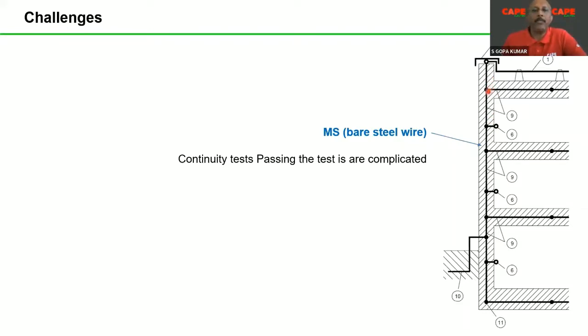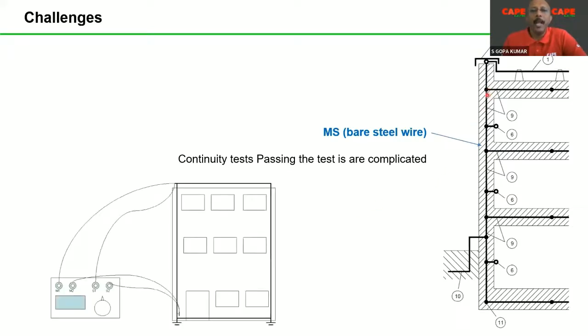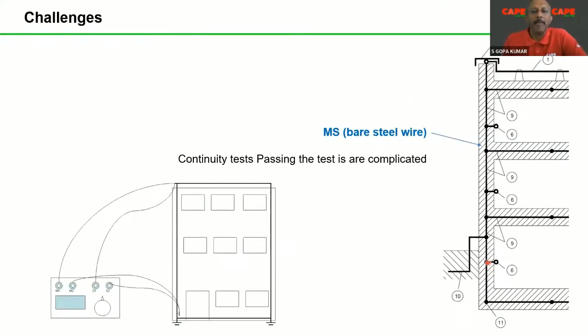In this case, out of our experience, what we are facing is after finalizing, after making this installation, we are supposed to check the continuity resistance. In several cases, the continuity resistance check is failing. Using MS is having that particular risk. Sometimes the required resistances are not possible, probably due to the corrosion or the kind of the joints are not proper and so on. So MS material is also having a risk. Please understand that after casting your steel or after construction, you cannot change anything. So if you wanted to make some modification, impossible.